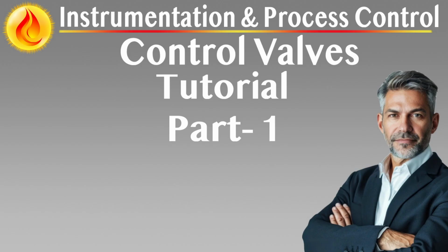Angle valves. These are ideal for services involving coke formation, erosion, e.g. slurry transport, flashing conditions, or solid-laden liquids. Angle valves are also used where outlet velocities must be minimized. Specialized choke valves for wellhead use fall under this category.